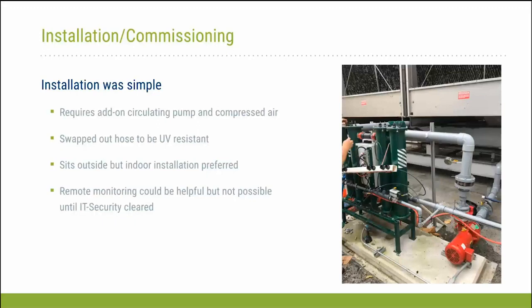When I initially scoped out the unit, the vendor was using electric valves. There's 3 valves on the unit, and they were electric actuated. They then switched to compressed air, and so the project got awarded before we knew about the compressed air requirement, and so they installed that on site with the contractor. We found out that that particular hose they used was more of a shop hose or shop quality hose that really wouldn't be good long term outside with UV rays on it.